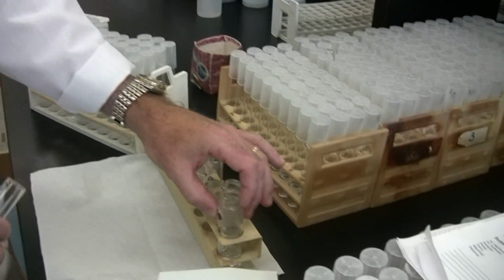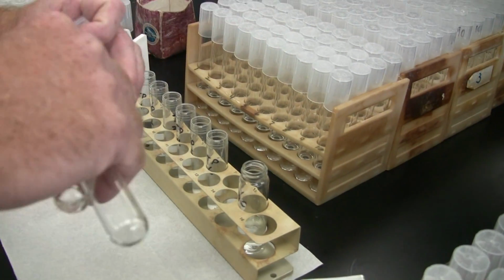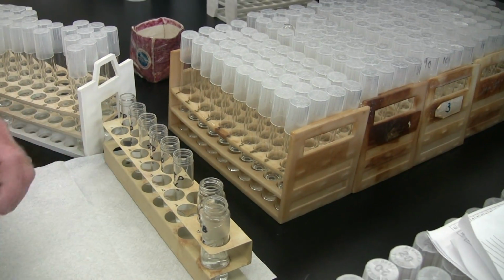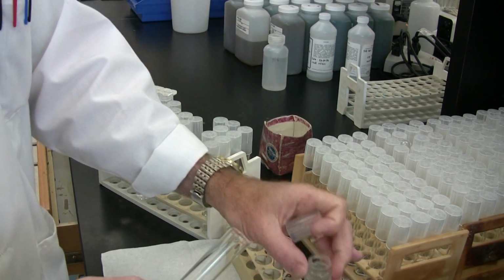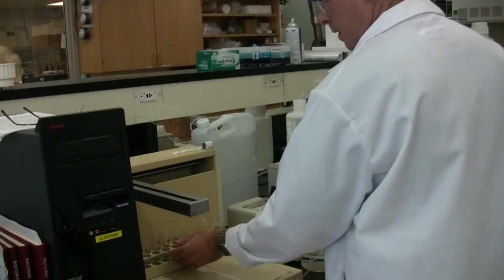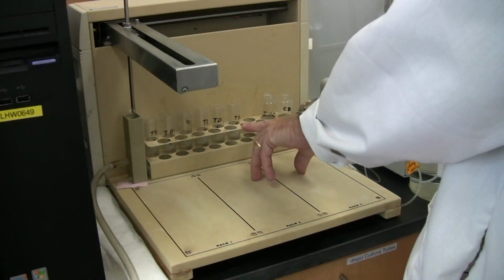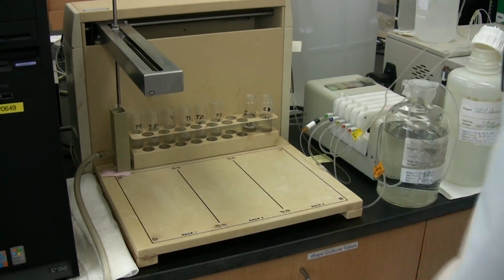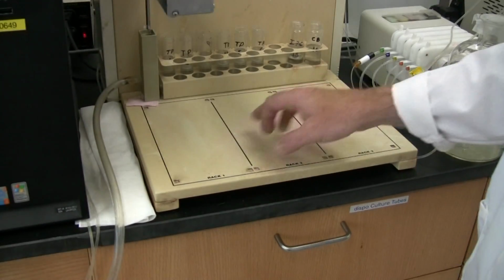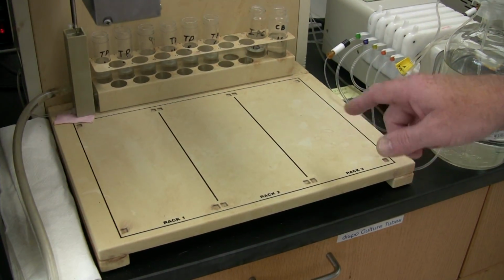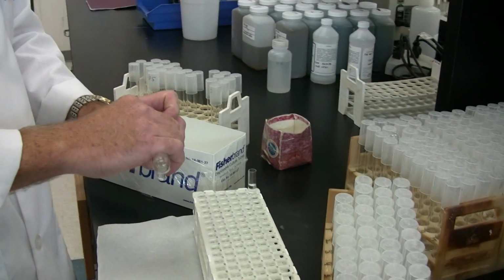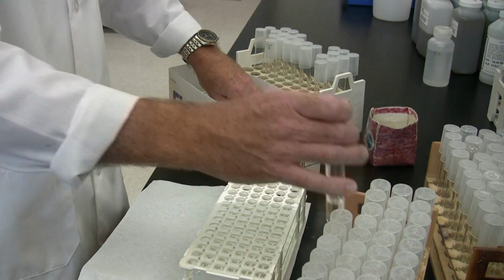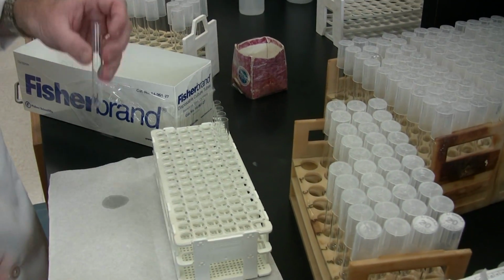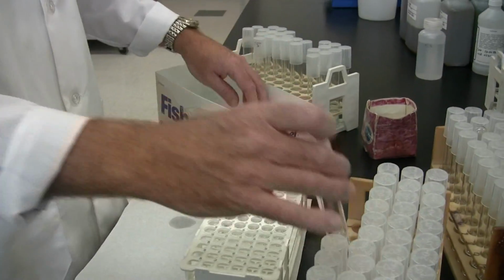These larger ones at the end, it'll run one every 10 unknowns. It's a check standard and a check blank just to show the instrument is still in calibration and has not drifted. And this is what we call our standards rack, because these are only standards, and it'll go back there to establish our curve. These spots, 1 through roughly 280 or something, are where we'll put the samples. So each one of these test tubes has a slot which lines up with the numbers that I showed you before on the piece of paper. This is the not so exciting part. I have to pour 186 larger tubes into smaller tubes, but that's the only way it all fits.